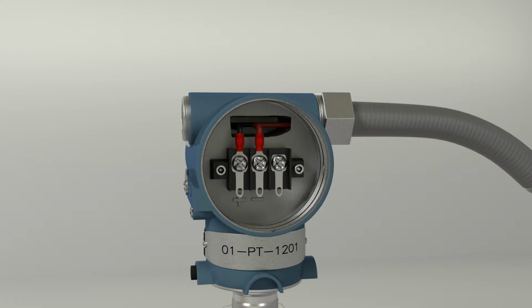Loosen the screw terminals where the wires are landed in the transmitter, being careful that while loosening the transmitter screws, the shaft of your screwdriver does not touch the transmitter casing. Then pinch the wire or crimp-on connection of the positive wire and gingerly lift it up. This may require some light wiggling side to side. Once the connection is free from the terminal, pull the wire straight out towards yourself, then up, being very cautious not to touch it to the housing.